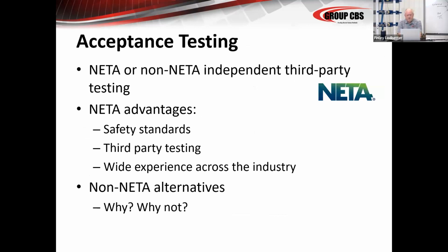Now, if we talk about the different ways to go about acceptance testing, and we're going to define acceptance testing as brand new equipment. It may have been in storage for some period of time. It may not. So how long was it in storage? How was it stored? Was it stored properly? When you take it out to install it in the switchgear, are there any telltale signs you see: rodents, moisture, condensate, damage? All that stuff needs to be checked very closely before it's installed in the switchgear because your warranty has started to run at some point along the way.